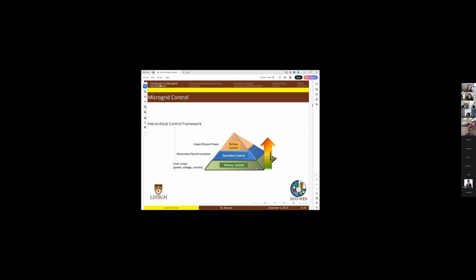The primary control is in charge of controlling the voltage and currents and also the active and reactive powers that you basically get out of a device within a microgrid. This is a very fast control, meaning it's going to happen in a few milliseconds or a couple of milliseconds. Then you have the secondary control, which is basically trying to synchronize your components to the main grid or compensate the mismatch between the voltage and frequency that your DER or inverter-based resource is causing when it's connected to the main grid. So the secondary control is going to compensate for that.